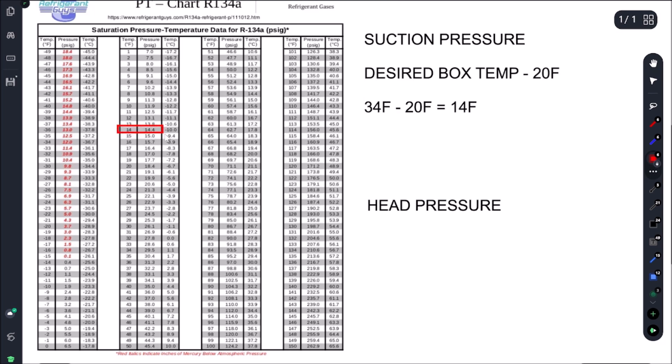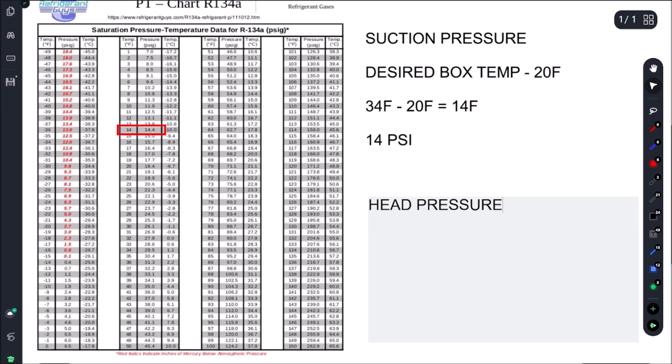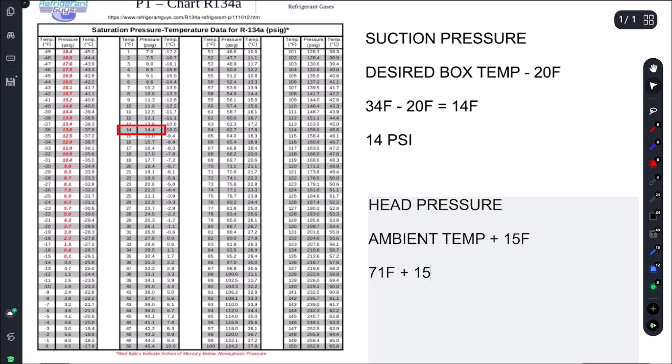To find our head pressure, we're just going to simply take our ambient temperature and we're going to add our condenser split. So in this case our condenser split is 15 Fahrenheit. Our ambient is 71 Fahrenheit, we're going to add 15 and that's going to give us 86 Fahrenheit saturation temperature. So let's pull up our PT chart one more time. 86 Fahrenheit is going to give us 97 PSI.